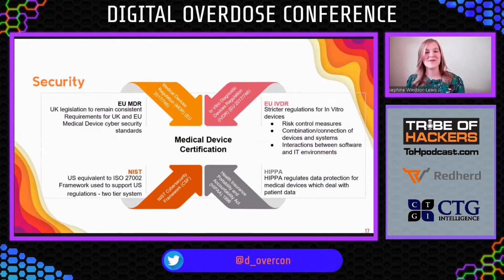Besides the point, this is also a medical device. Medical software counts as a medical device in most countries around the world, and therefore it needs to pass medical device certification standards. These vary around the world. Up here, I've put just 4 basic laws from the UK, EU, and the US. In order for a medical device to be made available in a country, it has to be certified.